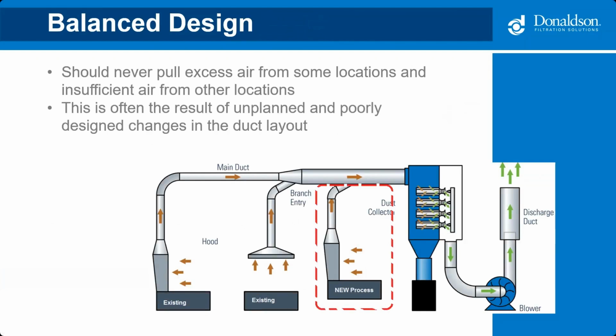Having a balanced system is one of the most important aspects of an effective dust collection system. It ensures you are pulling the required amount of air from each hood. To do this, the energy needs for each leg of the system at a junction must be the same. Neil, do you ever run into this in the field? Yes, it's actually very common. Usually customers add a new piece of equipment to an existing system and don't consider the impact it has on the existing equipment. Originally these systems are designed for a specific number of machines or equipment, and as you add to that, like I said earlier, you can throw things out of balance pretty quickly.